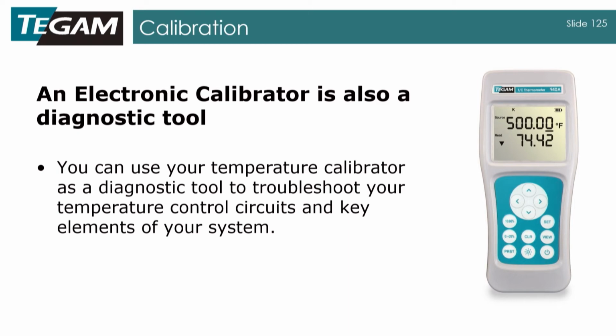Not only can you use a calibrator to monitor your measurement circuit, but sometimes you're also monitoring a control circuit. So if you've got a freezer keeping something cold, or a heating system keeping something warm, you can use a calibrator to watch the process and see whether it's overshooting, how it's maintaining over time. You can also use a data collection thermometer for some of that as well.